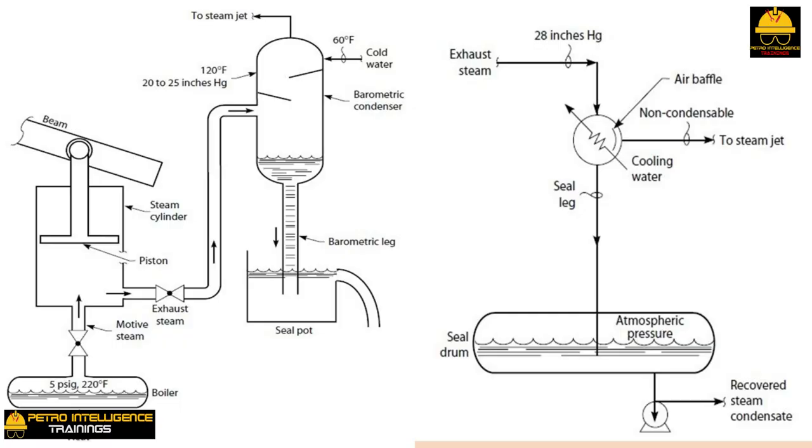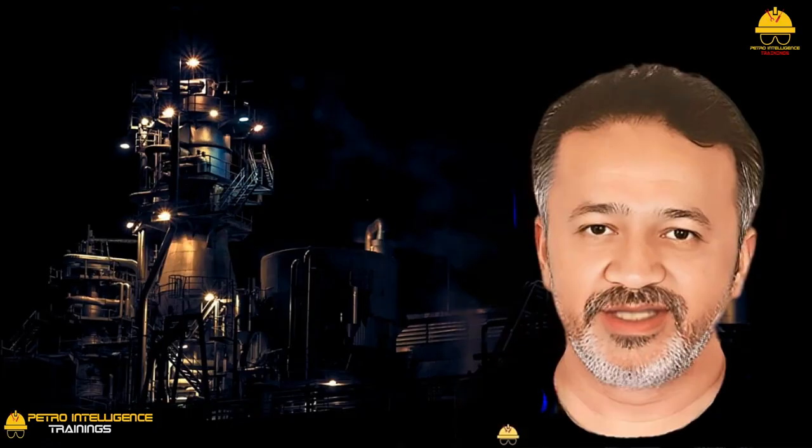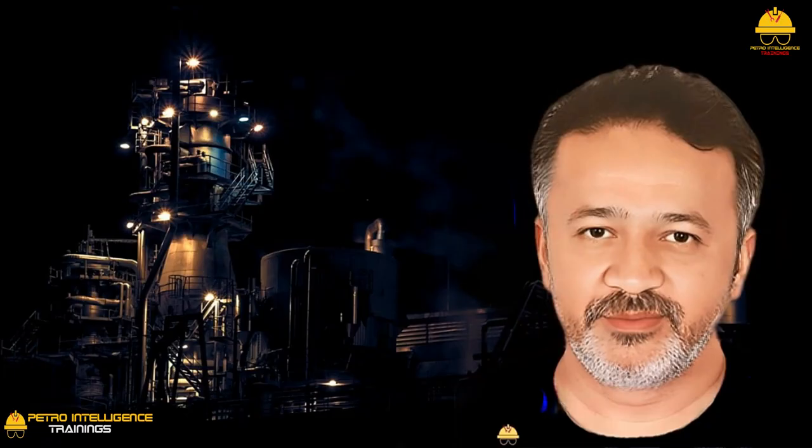The cooling water supply to the barometric condensers was naturally seawater, which mixed with the steam condensate. The solution: do not condense the steam by direct contact with cold water as done in the barometric condenser — instead, condense the steam by indirect contact with the cold surface of tubes in a shell-and-tube condenser, hence the name 'surface condenser.' Other than recovering clean steam condensate for reuse, there is no difference at all.